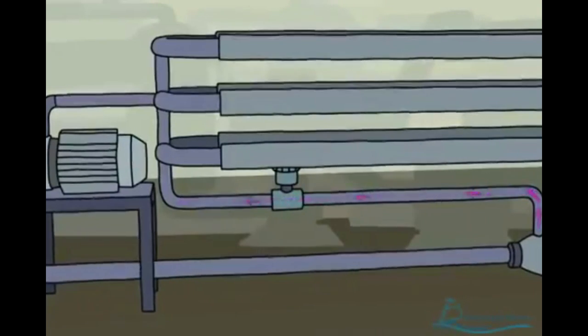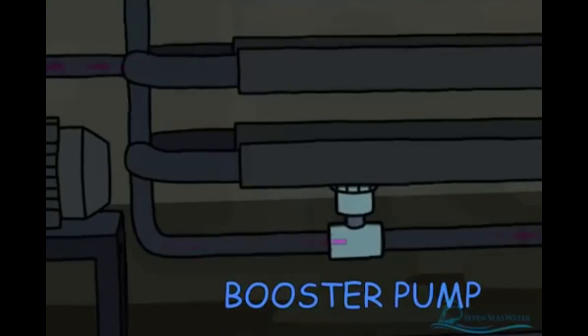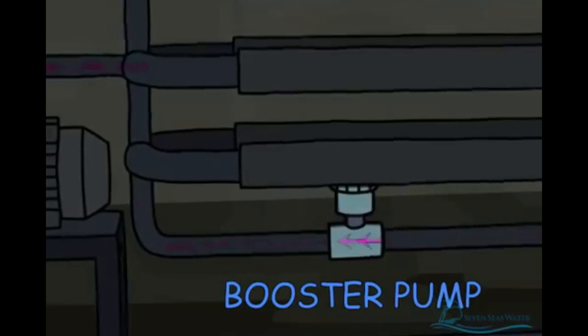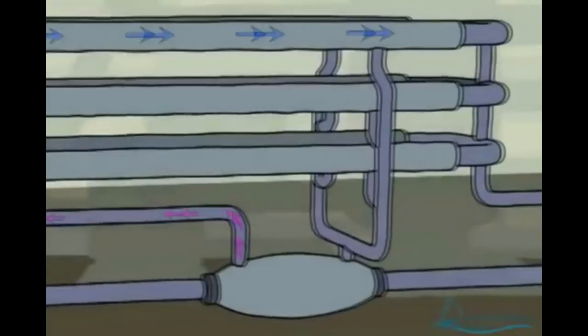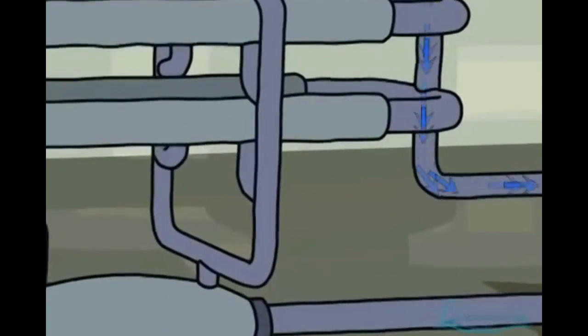The pressurized seawater leaving the energy recovery device has its pressure boosted by a small booster pump so that it is at the same pressure as the seawater leaving the high pressure pump. The boost is necessary as some pressure has been lost as the stream travels through the reverse osmosis system. Approximately 40% of the seawater that enters the system is converted to potable water during the reverse osmosis process.